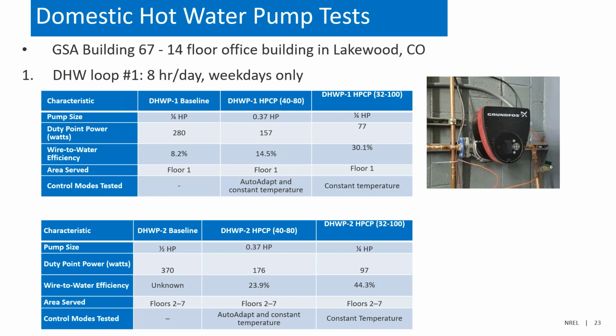So the first test case that we looked at was a domestic hot water recirculation system. This was installed on a 14-floor office building in Lakewood, Colorado. The domestic hot water loop number 1 served the first floor, a cafeteria. The domestic hot water pump number 2, that second table there, is serving floors 2 through 8 of the building. Again, they're set up as a domestic hot water recirc to provide hot water to the domestic hot water loads on those floors. We have a three-quarter horsepower baseline pump for the first one and a half horsepower pump for the second one, and the model 4080 doesn't directly correlate to the same horsepower ratings, but it's around 0.37 horsepower, and was still oversized for the load.